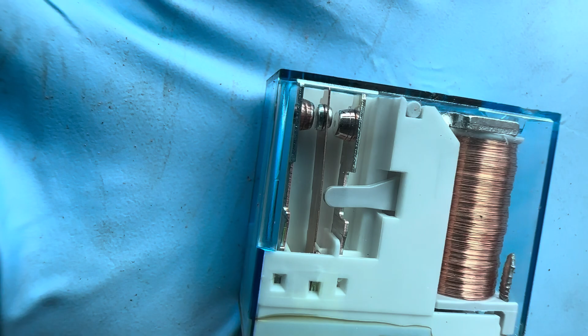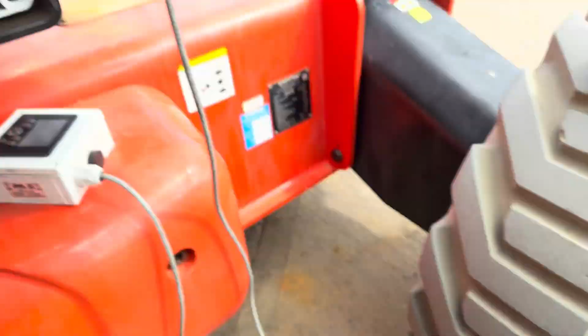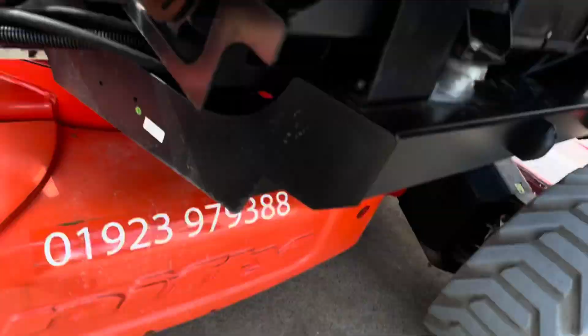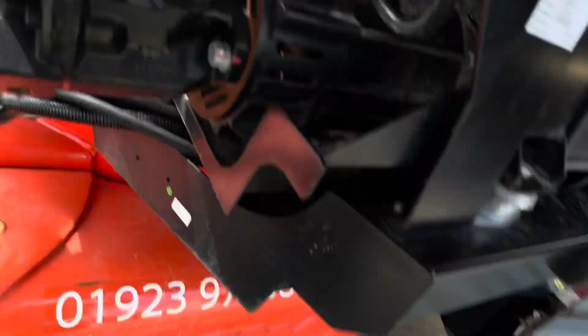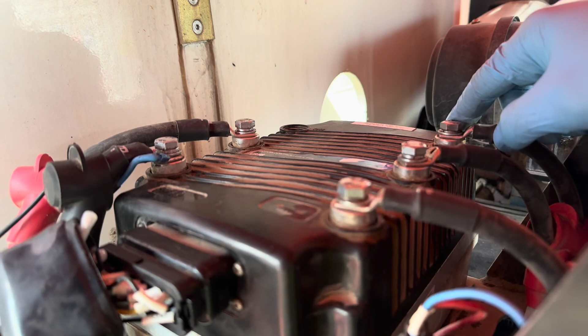Okay, but that doesn't stop us going and investigating further. I think it's just for the sounder, so it has to be fixed obviously, but it's not stopping us from continued diagnostics with the CAN bus. So we know that if the motor controller is disconnected, the machine works fine. So that makes me think that there is a fault in the motor controller. It's just because if you don't switch this on, then the machine kind of works, or doesn't present error 27, which is communication error. So it seems to me like this device is faulty.